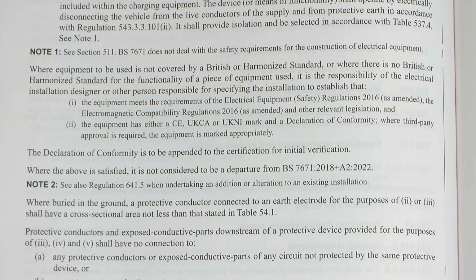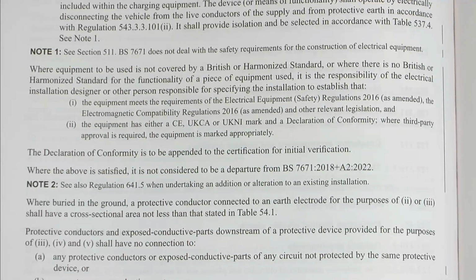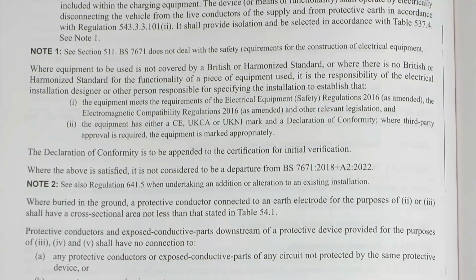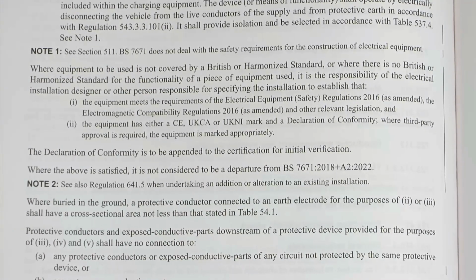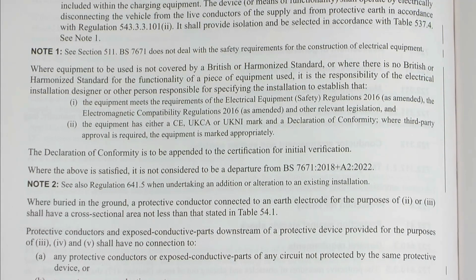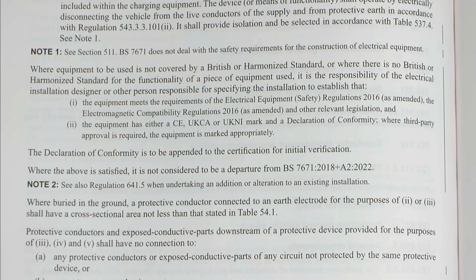Now, this is here because a lot of the equipment which has been on the market for some time, which various people are selling for various types of protection, including things like the open conductors and all of that kind of thing, doesn't actually comply with the standard because there aren't any standards for it, because people haven't either written them or whatever. So what this is saying is that in the event of using some of those pieces of equipment, you need to get from the manufacturer the declaration of conformity, make sure the equipment is appropriately marked, and of course the manufacturer can then advise whether it complies with those particular directives, which basically are EU directives converted into the law in the UK. So you need to get that from the manufacturer and then attach it to your certificate for the installation.